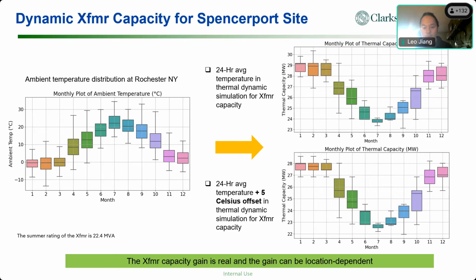If you look at the shoulder months, like March, April, May, September, October, the transformer could easily gain a few megawatts of capacity because of the lower temperatures. So basically the transformer capacity gain can be real, and the gain can be location dependent. You don't anticipate a similar benefit if you move to the southern states. But in New York, yes, we will definitely see some additional capacity.